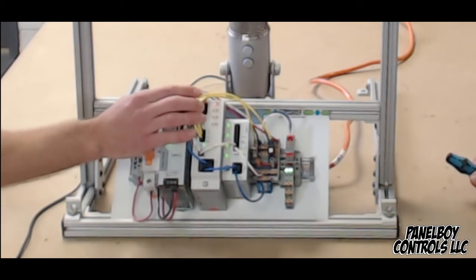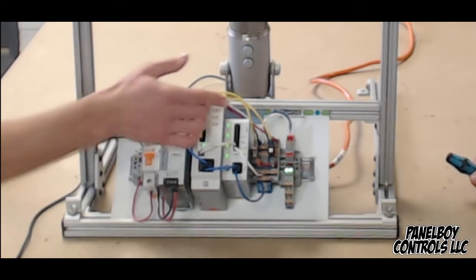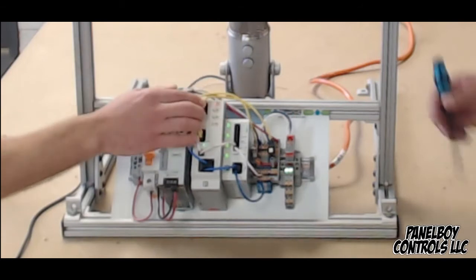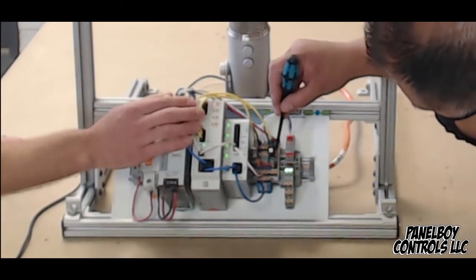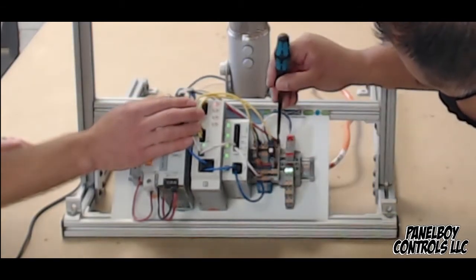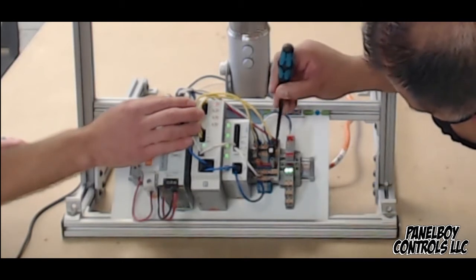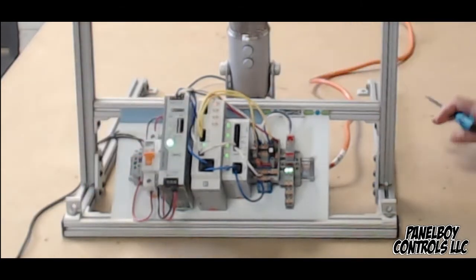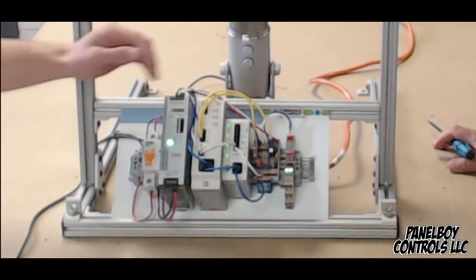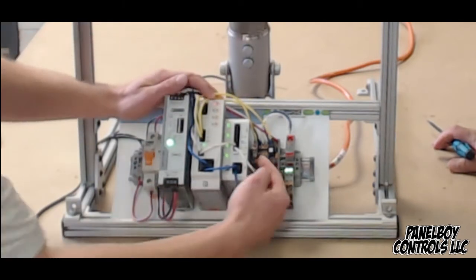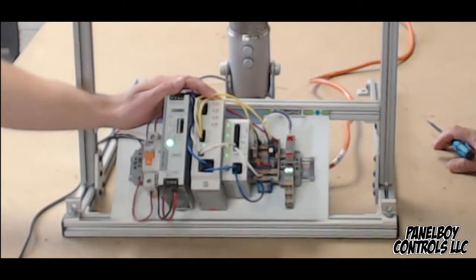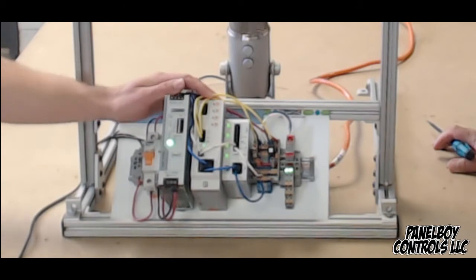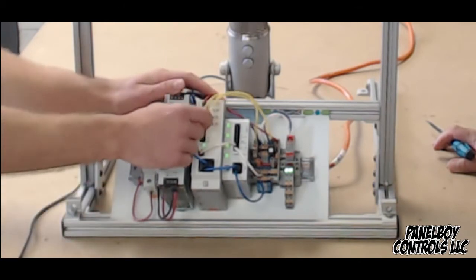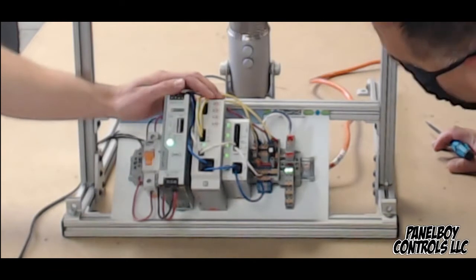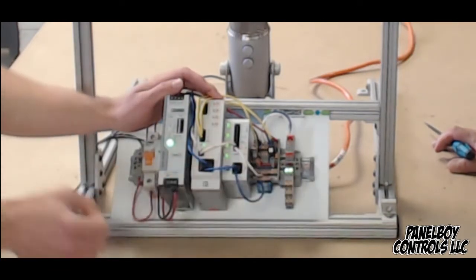You'll notice it didn't reset. That's because we still have the short circuit enabled. So if you want to open that knife disconnect up, there you go. So I can reset it now by pressing that button, or there's actually a little push button now wired up here. And what that does is apply 24 volts to the reset input. Okay. If I press and hold, it's not going to reset it. I have to let go of it.